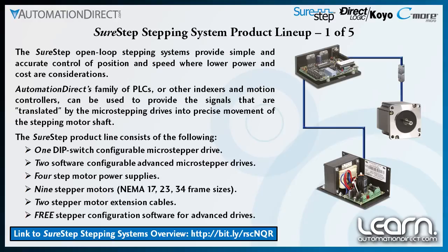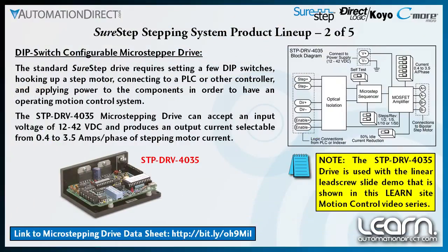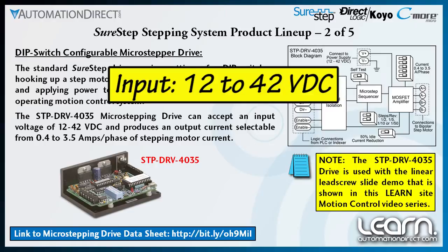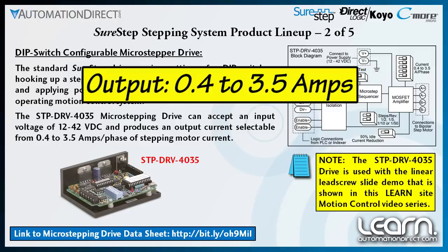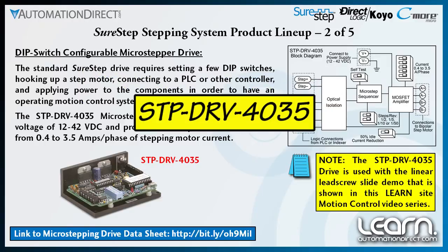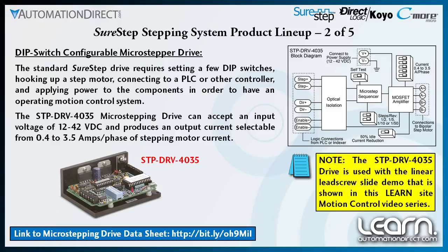The signals translated by the micro stepping drives into precise movement of the stepper motor shaft can be provided by AutomationDirect's Do-more family of PLCs or other indexers and motion controllers. The dip switch configurable micro stepper drive can accept an input voltage of 12 to 42 volts DC and can produce a selectable current from 0.4 to 3.5 amps, which is the stepper motor's current rating per phase. I'll be using part number STP-DRV-4035 as part of my motion control demonstration, and will cover it in more detail in the part 4 video titled 'Wiring, C-TRIO Jumper Settings and Drive Dip Switch Settings.' With a few dip switch settings, wiring up a step motor, connecting to a controller, and applying power, we can have an operating stepping system in short order.